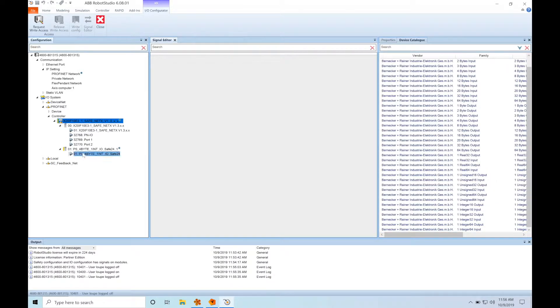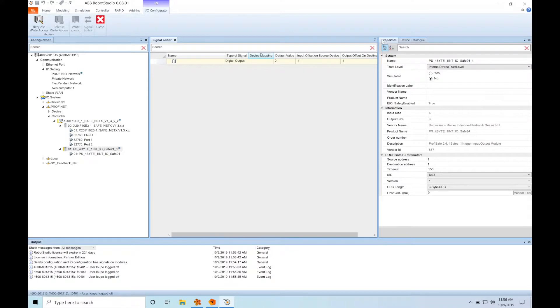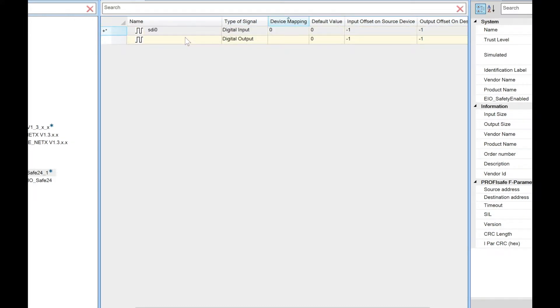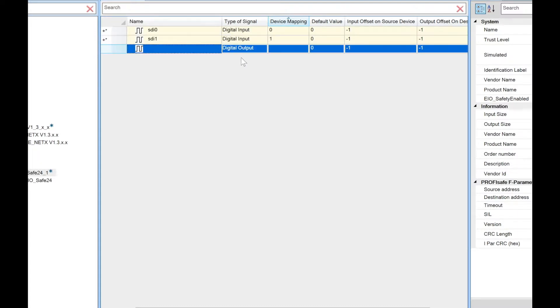This virtual module is a ProfiNet slave, so we have to configure it. We're going to do that by giving it a destination address, which we will use later on the B&R side. In this case, I'll arbitrarily pick a value of 10. And for fun, I'll change the SIL rating to 2. Now we have to configure what we're going to be passing over the ProfiSafe network. I'm going to create two safe digital input signals on the ABB side: one called SDI 0 and one called SDI 1. SDI 0 will correspond to our area scanners in an AND configuration, and SDI 1 will correspond to the e-stop.